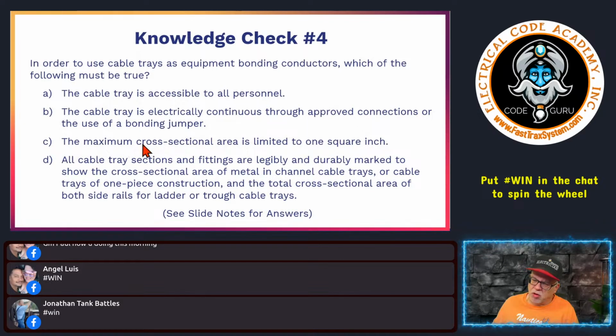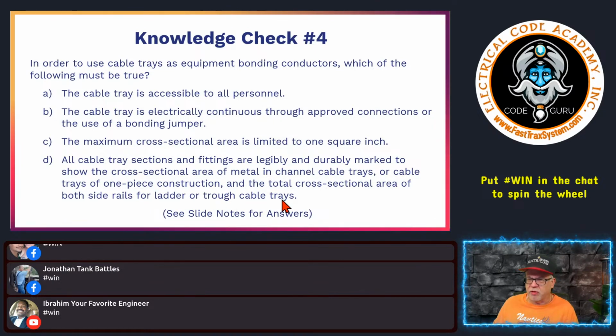The maximum cross-sectional area is limited to 1 square inch. All cable tray sections and fittings are legibly and durably marked to show the cross-sectional area of metal channel cable trays or cable trays of one-piece construction, and the total cross-sectional area of both side rails for ladder or trough cable trays. Okay, so first one, it's not all personnel.